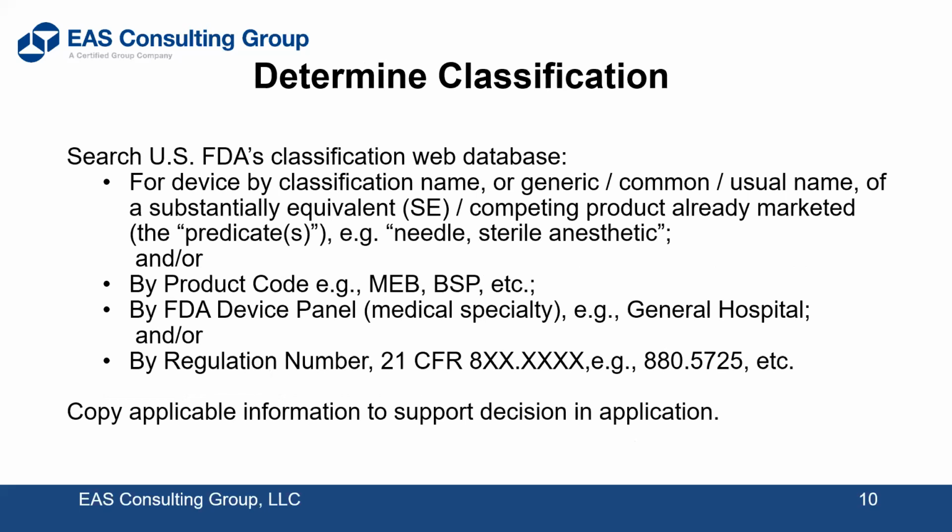Those acronyms have no bearing on their use other than they're tied to it. I had one FDA person years ago say it was based on the initials of the initial person that handled that particular panel or product. I don't know if that's true or not, but it seems to be the most reasonable definition for the acronyms that are used. They don't stand for the actual product. They're connected to a specific product or class of products, but the acronym doesn't match the product, let's put it that way. So that could be confusing. You have to go purely by the regulation number to tell you what the product code is.